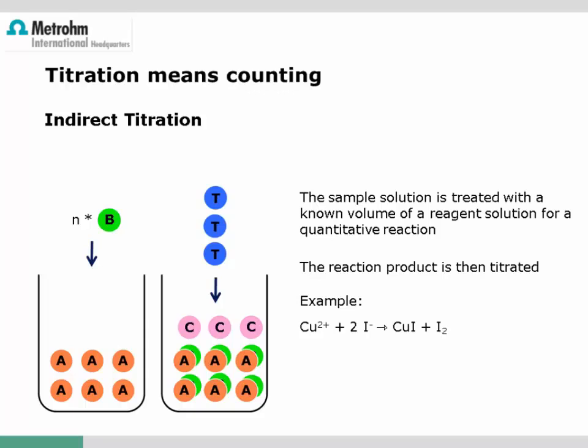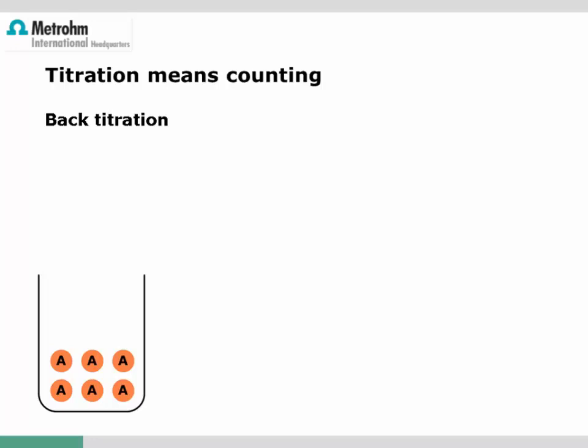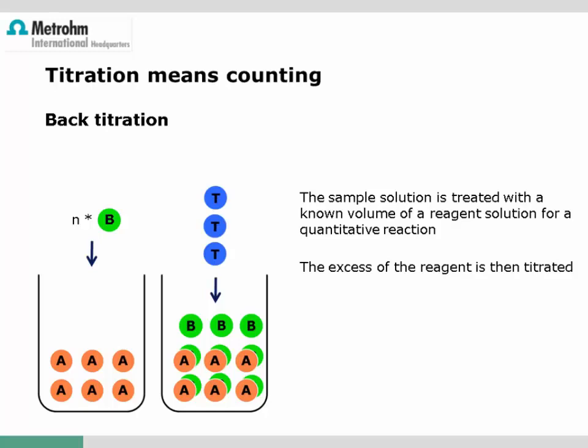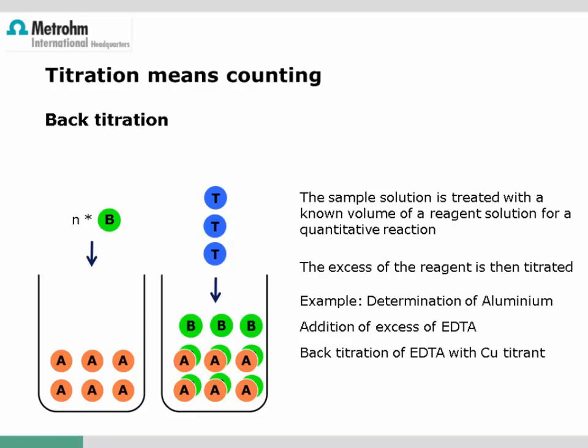One example is the titration of bivalent copper ions. A known amount of potassium iodide is added to the sample solution, which enforces the reduction of the bivalent copper, generating iodine. This iodine is then titrated in a redox titration using thiosulfate solution. Another indirect method is the back titration: the analyte solution is treated with an excess of reagent solution, and the excess reagent is then titrated directly. A typical application is the determination of aluminum, since no suitable sensor is available — the aluminum solution is treated with excess EDTA, and the remaining EDTA is titrated with a copper solution using a copper-sensitive electrode.